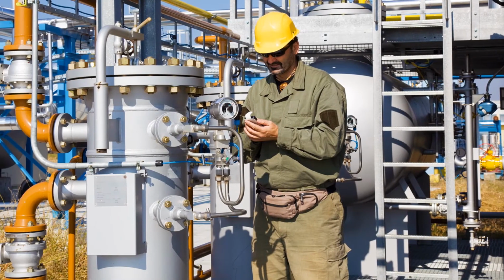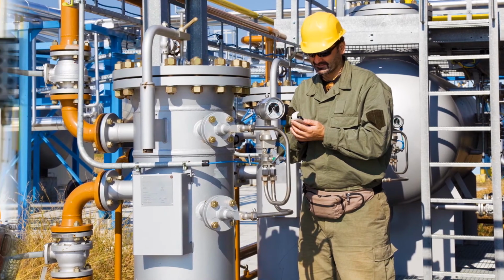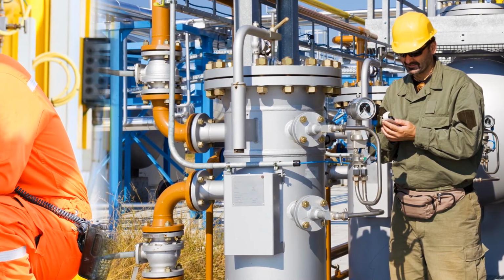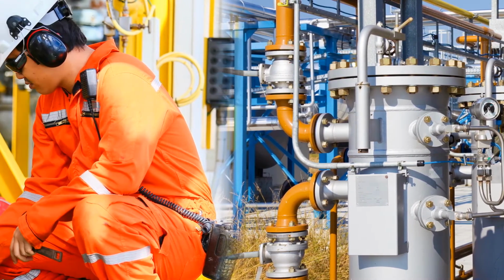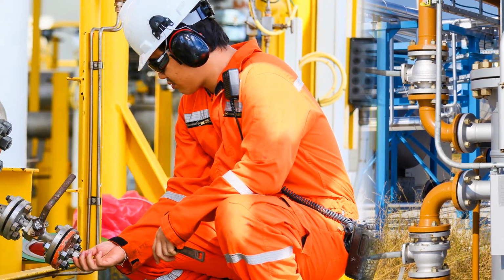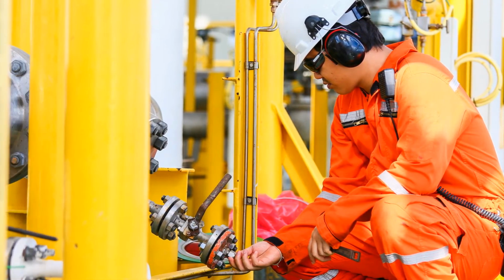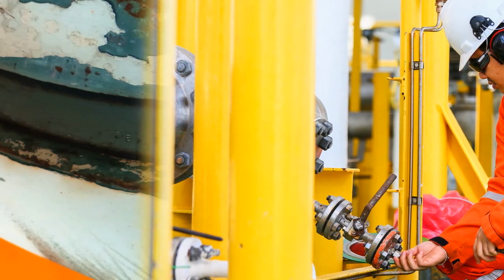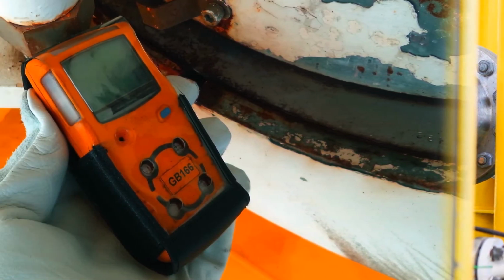Regular testing is important because harsh and rigorous conditions break down the effectiveness and reliability of a device. You should also know when sensor failures occur from sensor ports becoming clogged. Testing should be done daily before any job is performed. It's not enough to test here and there. Regular monitoring will tell you if there are changes over time that you need to plan for. It's often overlooked, but it only takes a minute to do.